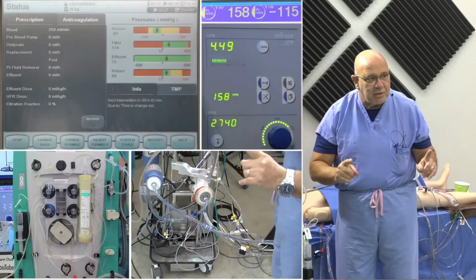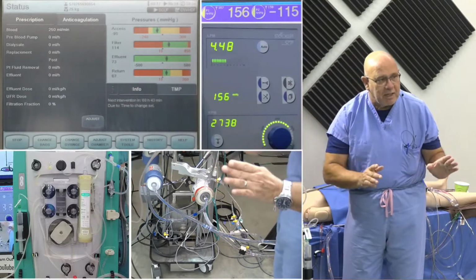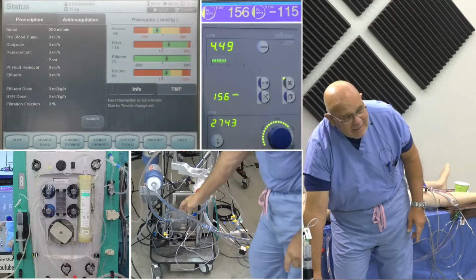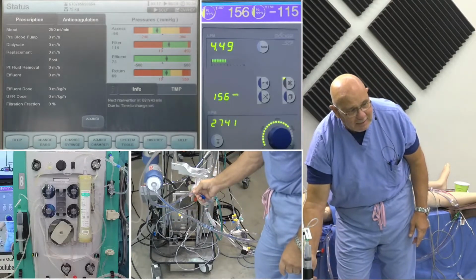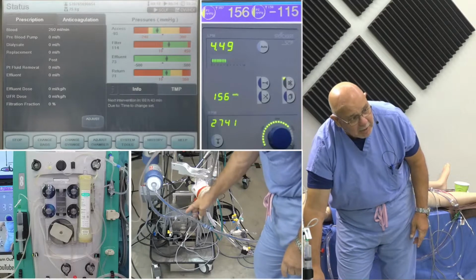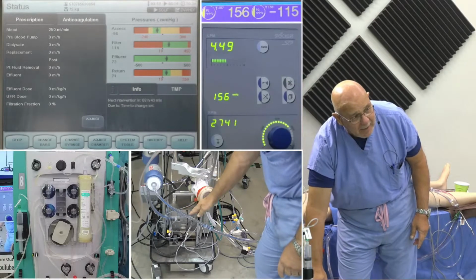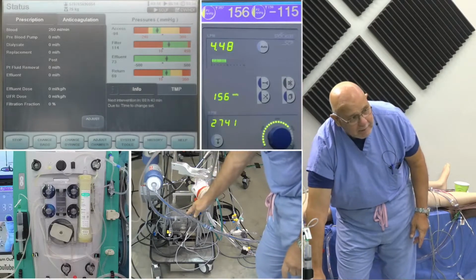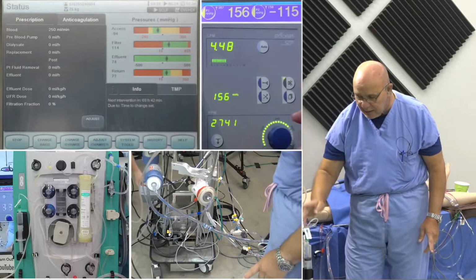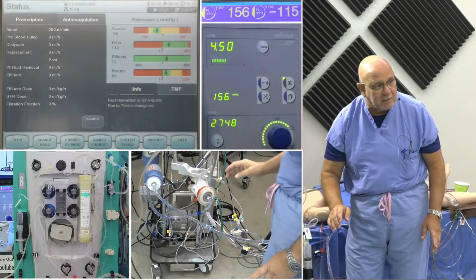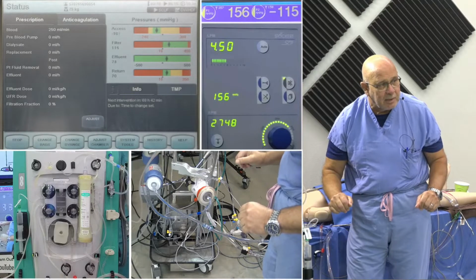So what I'm going to do now is measure the pressure in this line that I talked about, which is the line with the highest pressure at the same flow, and compare it with the same transducer and compare it to what we see there. So that's good. 156 is perfect. Let's let it settle out.